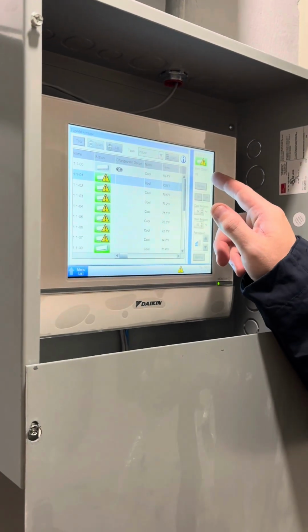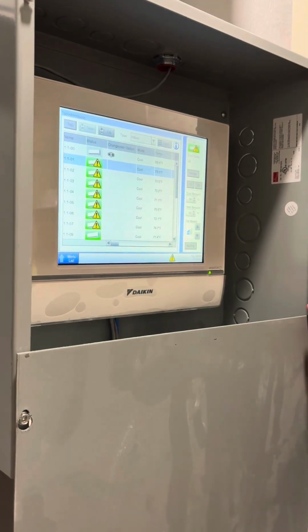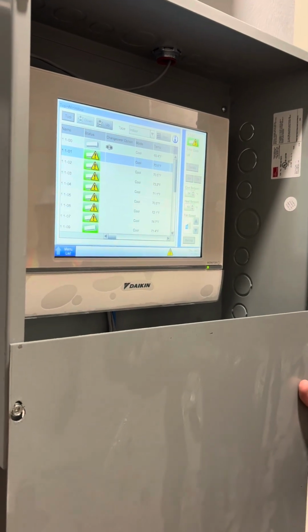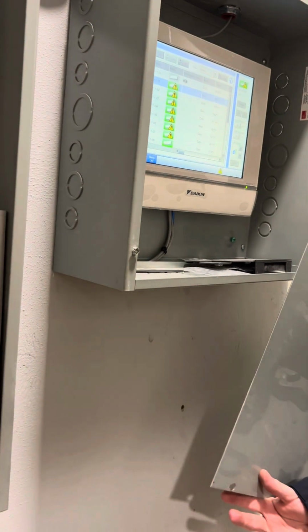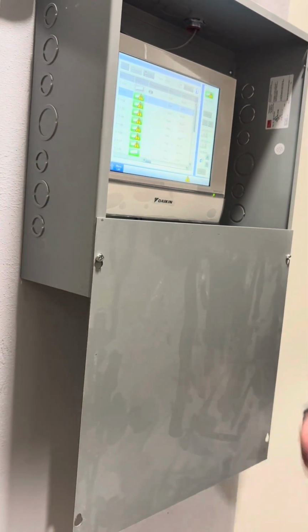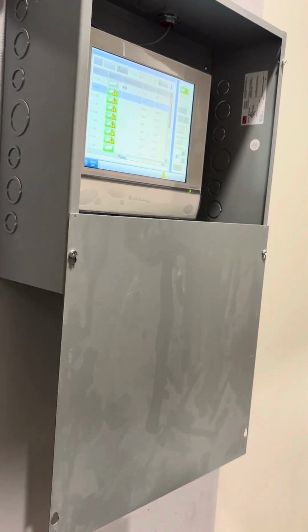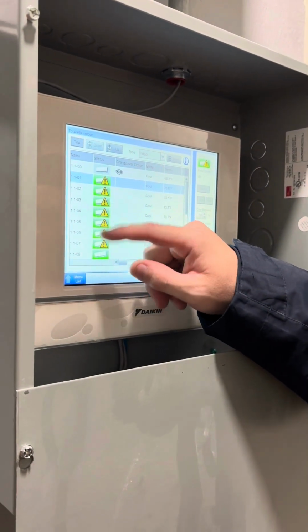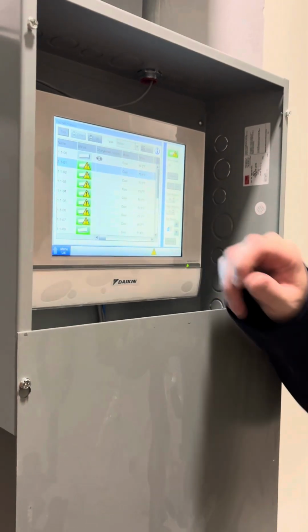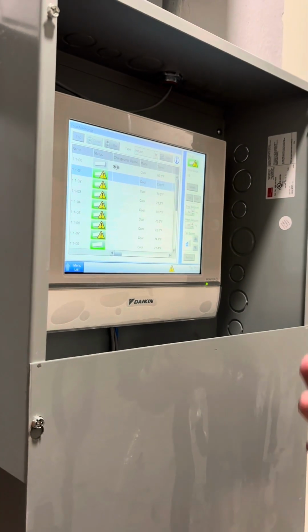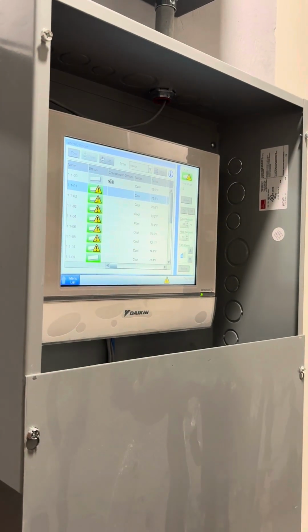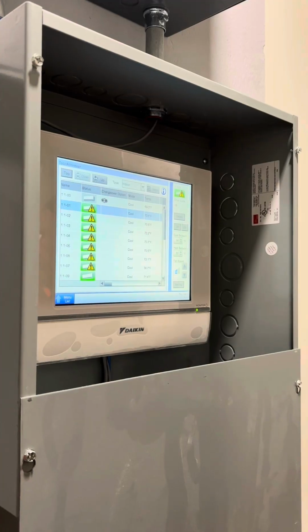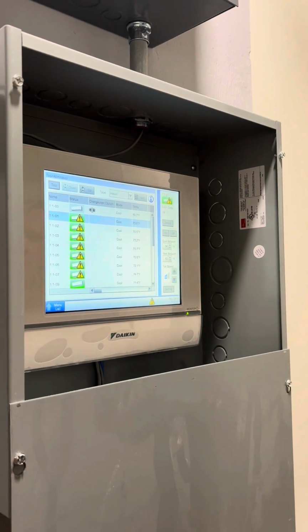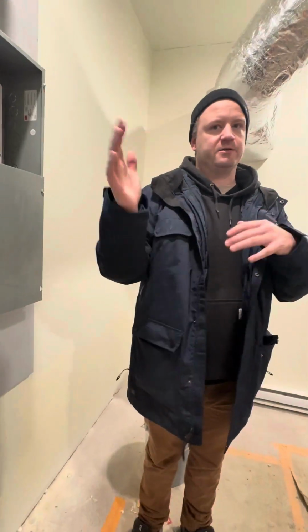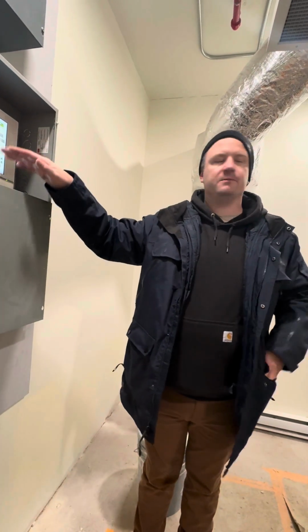I'm going to leave this U9 on you guys just to make sure that all of the indoor units are powered back up. If it stays like that, then let us know. Usually a U9 means somebody shut the power off. If you ever have a situation where these won't go away, a standard procedure would be to shut all the indoor units off, shut your outdoor unit off, turn all of your indoor units on at the breakers, and then turn your outdoor unit on. That will reinitiate a search for all of the indoor units. They'll start talking again, and then likely that goes away.